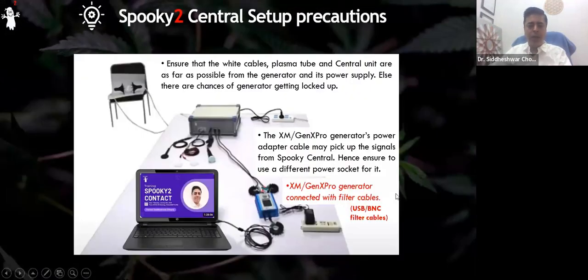The third point I forgot to mention: these generators are connected to the central unit using filter cables. The filter cable has to be connected such that the metallic ring is closer to the generator ports. You see here on the screen, the filter cables are always close to the generator - this one connected to the laptop, and the others connected to the central unit.